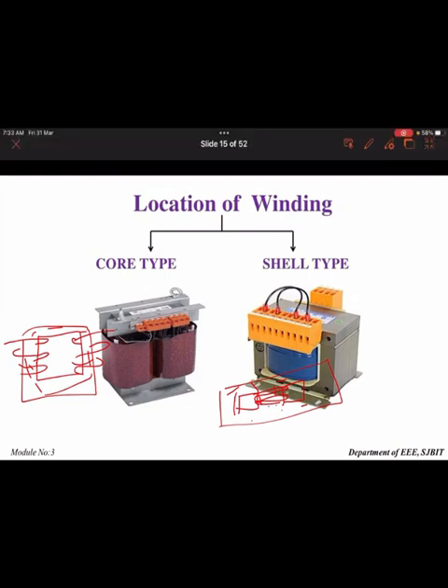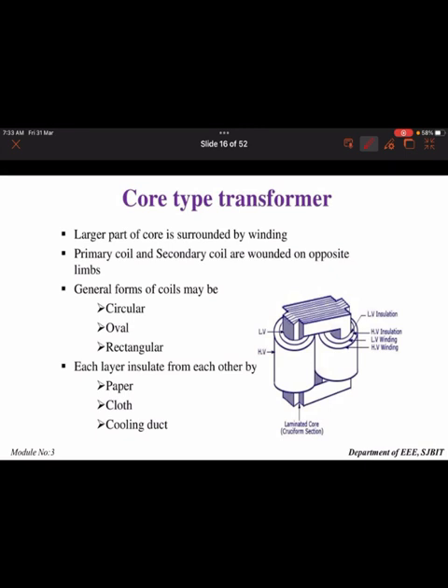In the core type, the primary winding is placed on one side and the secondary winding on the other yoke. As you can observe, on the core the winding is surrounded — the core is surrounded by the winding. The primary coil and secondary coil are wound on opposite limbs and kept separated. The coils may be circular or rectangular in shape. Between the thin lamination sheets, insulated sheets such as paper, cloth, or cooling ducts are used.